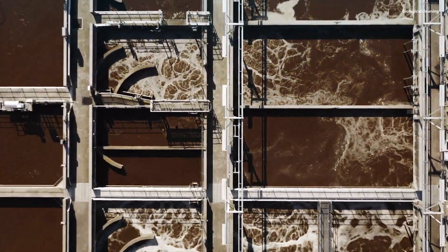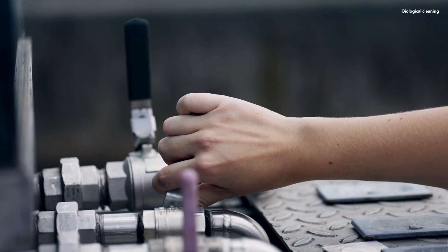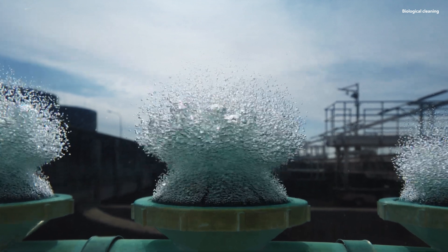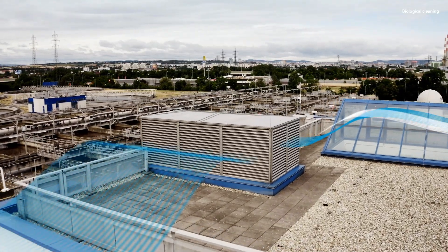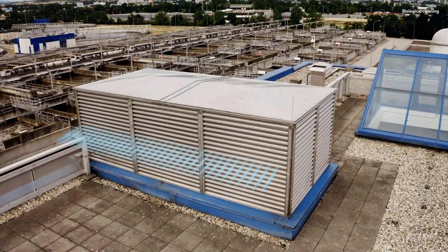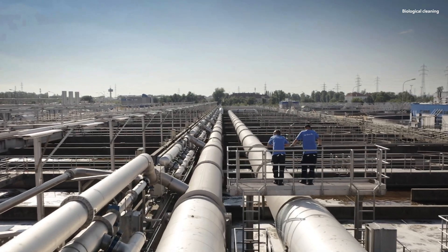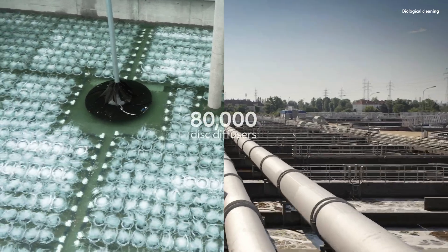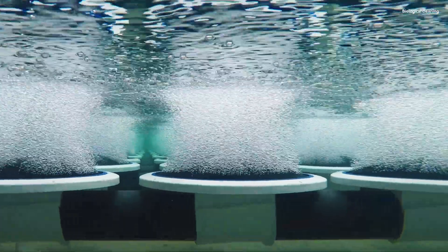However, inside these gigantic basins, everything happens on a bigger scale, much faster, more intense and highly concentrated. This process requires some external support. We humans and microorganisms have something in common: we need oxygen to stay alive. To supply the microorganisms with vast amounts of oxygen, ambient air is absorbed and densified in high-performance compressors. It is then streamed through huge pipes to the bottom of aeration tanks, where 80,000 disk diffusers distribute the air through fine-pored membranes, creating myriads of tiny bubbles.